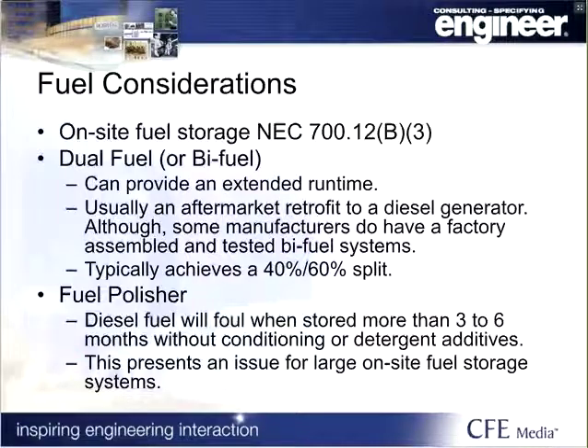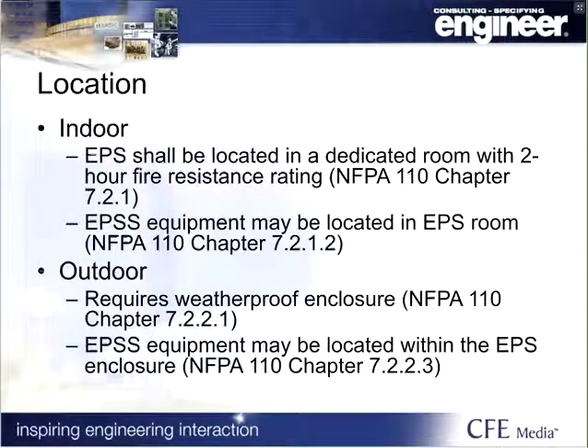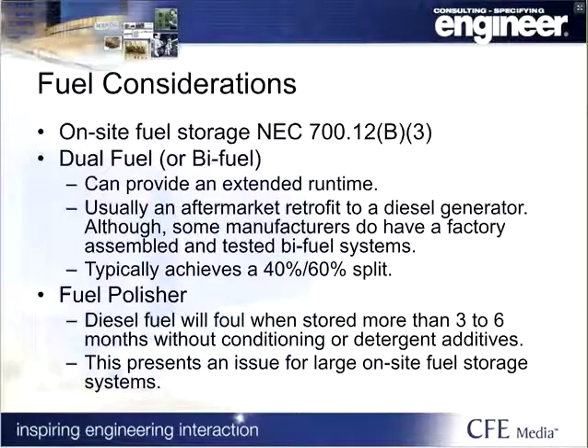When considering the fuel source, it is important to keep in mind NEC 700.12(B)(3), which requires the fuel supply to be located on the premise and prohibits the generator from being solely dependent on a public utility gas system. There is an exception where, at the AHJ's discretion, and where there's a low probability of loss of both power and public utility gas, this could be allowed, but it's not very typical. If you're looking to utilize natural gas as a way to increase your runtime but minimize your on-site fuel requirements, a dual fuel generator may fit the bill. Typically, a retrofit kit from a third-party manufacturer is field installed on a diesel generator. The kit is essentially a fumigation system where gas is mixed with the intake air and the diesel performs the spark ignition. This can significantly reduce the diesel consumption, typically getting a 40-60 split.